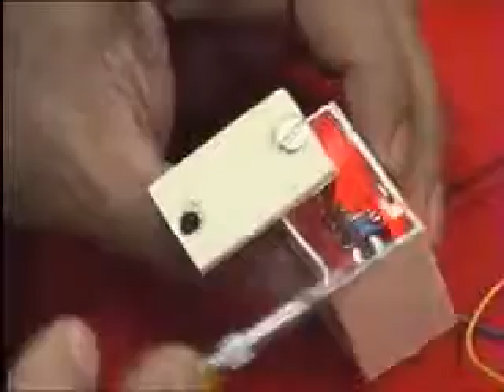If you see this small screw here inside, turning this switch clockwise will increase the sensitivity, and you'll see the small green LED glowing inside. That LED shows the sensitivity, and turning it anti-clockwise makes it less sensitive. Do not make it oversensitive, because then it will give a false alarm.